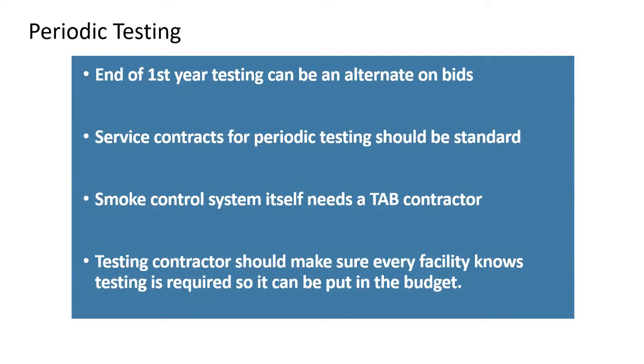I think the most important thing, and I'm sure Troy would agree too, is your main point of having that first year testing on the alternate bids is so important, so that it's not the maintenance team that also has to scramble to take care of it. It promotes definitely a team attitude to taking care of a capital or retrofit project and making sure that it captures that 1 year need for retesting. Especially on smoke control systems, where a lot of places don't have somebody that is capable of doing that. And so it's a great relationship to have with mechanical sheet metal contractors as a TAB provider or a CX provider or a consultant provider for smoke control systems to make sure that you take care of that need that's going to come up in such a short amount of time during that warranty period.